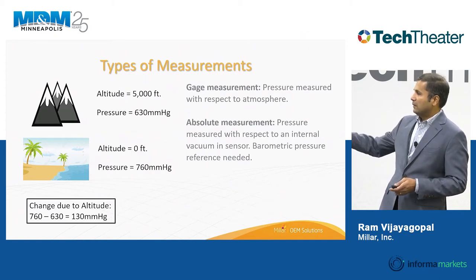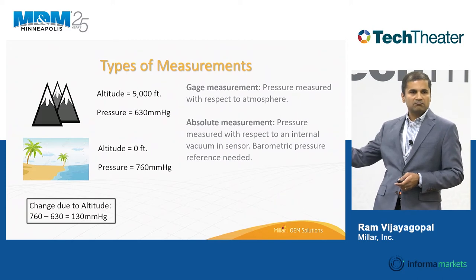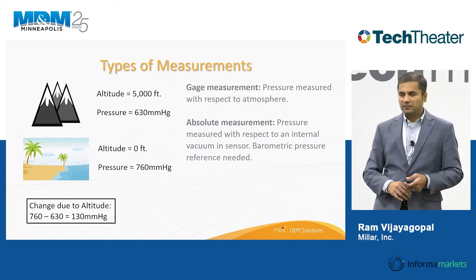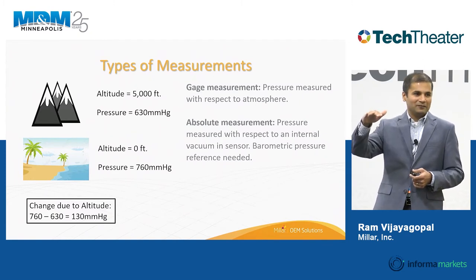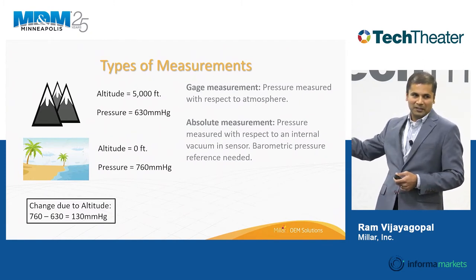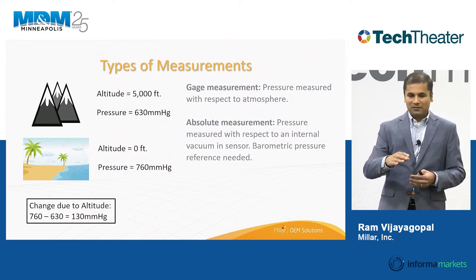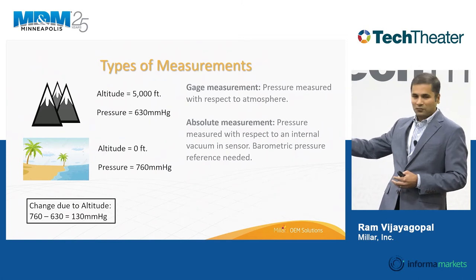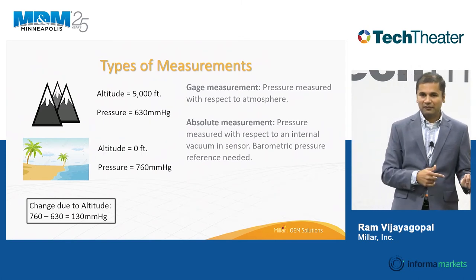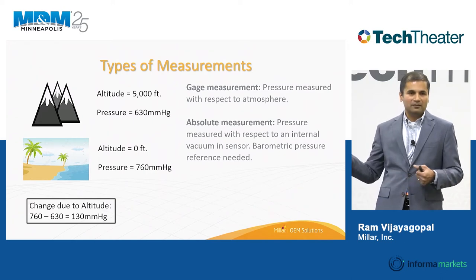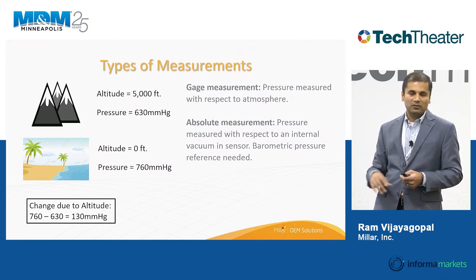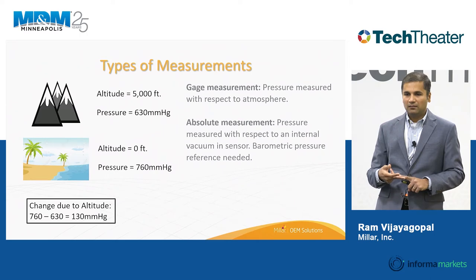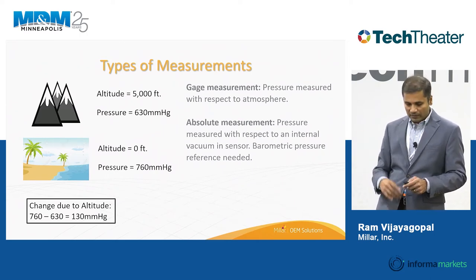As an example, a sensor at sea level in Houston typically measures around 760 mmHg. If it's moved to a hospital in Colorado at 5,000 feet above sea level, you're now at about 630 mmHg — a range of 130 mmHg just by moving the patient. Device developers have to factor this in early on, as it plays into accuracy and product cost.